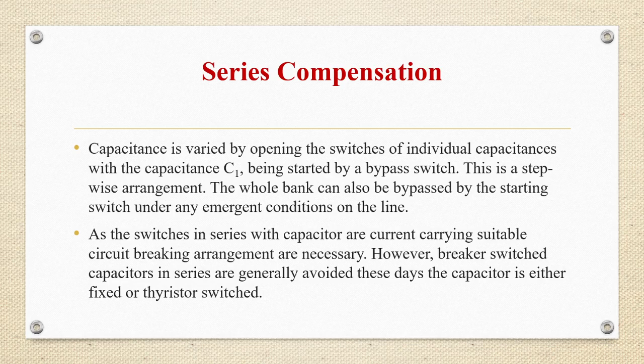As the switches in series with capacitors are current carrying, suitable circuit breaking arrangement is necessary. However, breaker switched capacitors in series are generally avoided these days, and the capacitor is either fixed or thyristor switched.